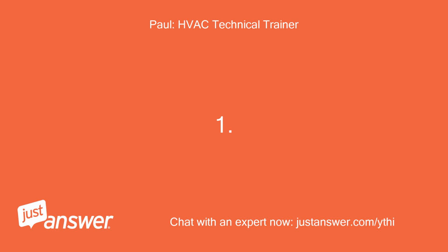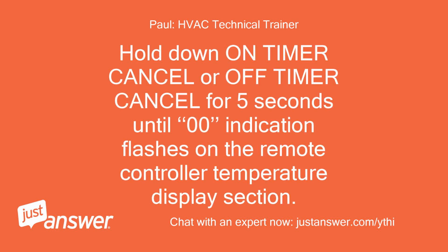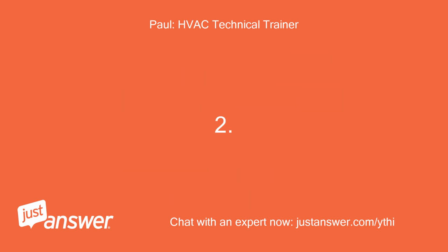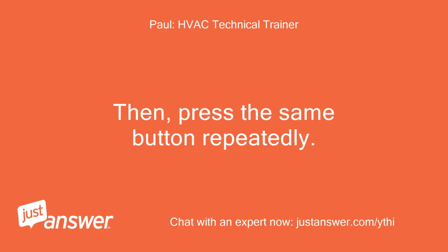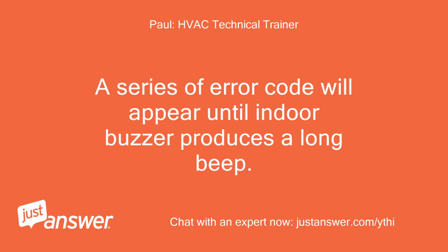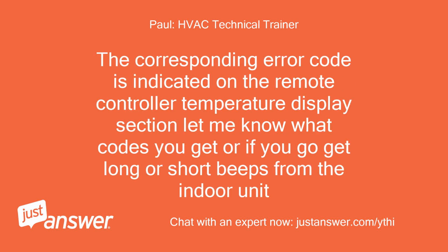Hold down ON TIMER CANCEL or off timer cancel button for 5 seconds until 00 indication flashes on the remote controller temperature display section. Then press the same button repeatedly. A series of error codes will appear until the indoor buzzer produces a long beep. The corresponding error code is indicated on the remote controller temperature display section. Let me know what codes you get, or if you get long or short beeps from the indoor unit.